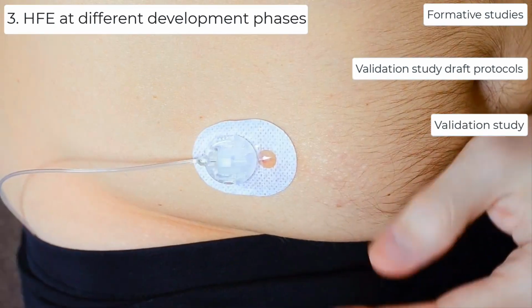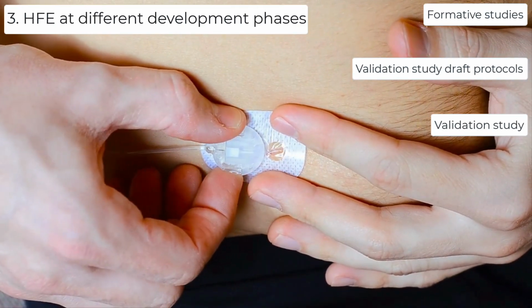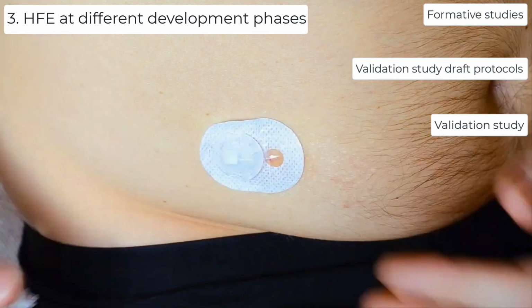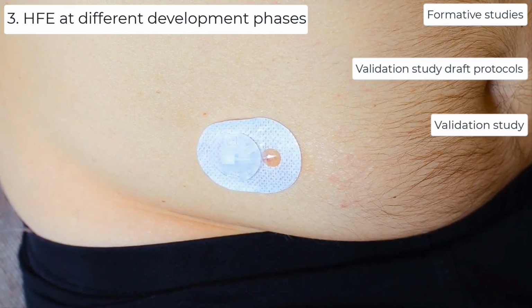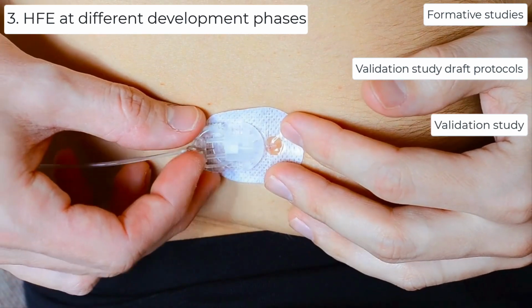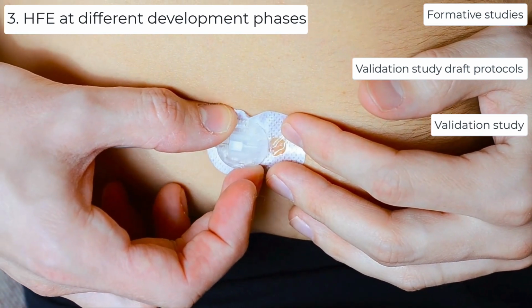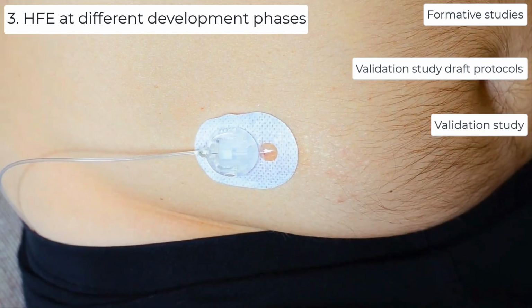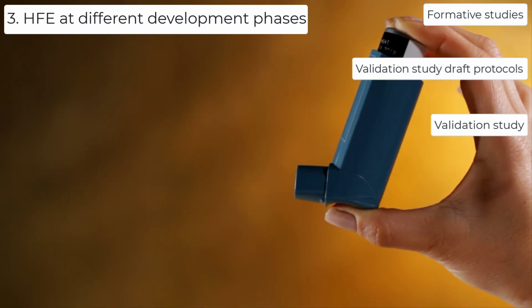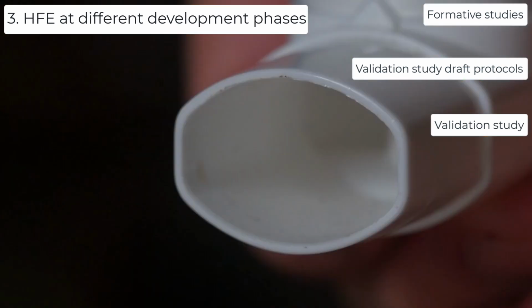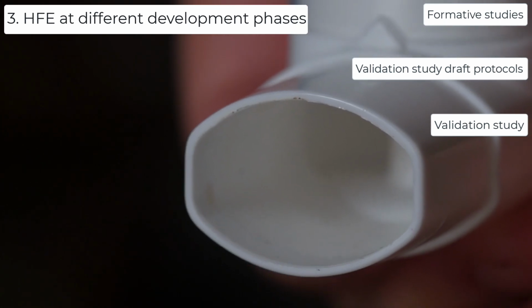Human factors actual use validation studies are conducted when simulated use test methods are not sufficient to evaluate user interactions with the final finished combination product. These studies assess the user interface of the device and are distinct from actual use or clinical home use studies that focus on clinical safety and effectiveness, where the user interface is not observed by a human factors evaluator.